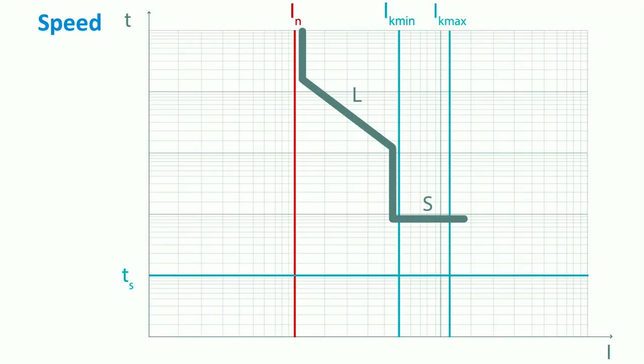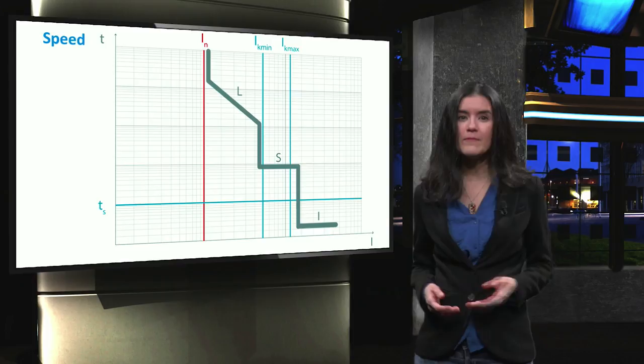The last region of the tripping curve is the instantaneous part and regards the essentially instantaneous trips at very high current levels. This very fast time reaction is reached generally during lightnings. In order to ensure correct tripping performance, the S part of the curve can be shifted downwards. This regulation increases the speed of the relay and its effectiveness when clearing circuit-related faults.